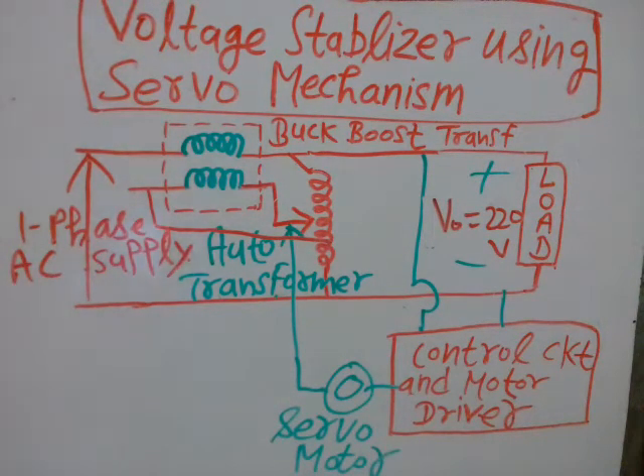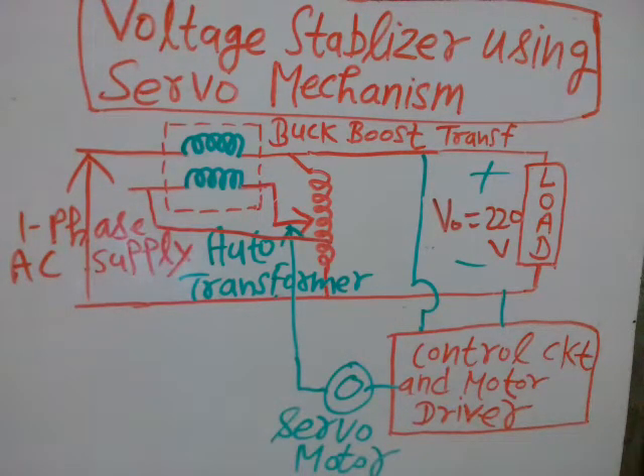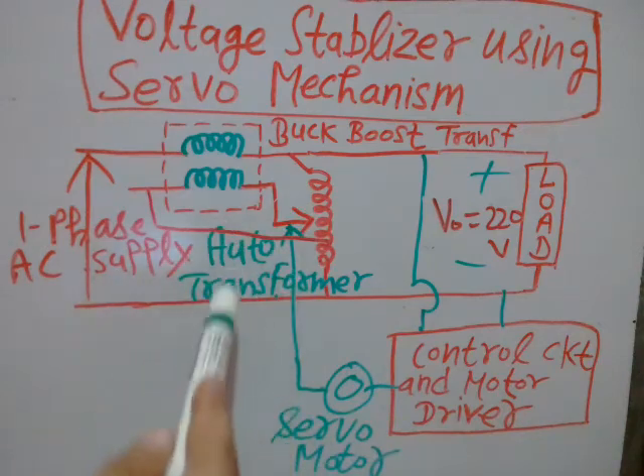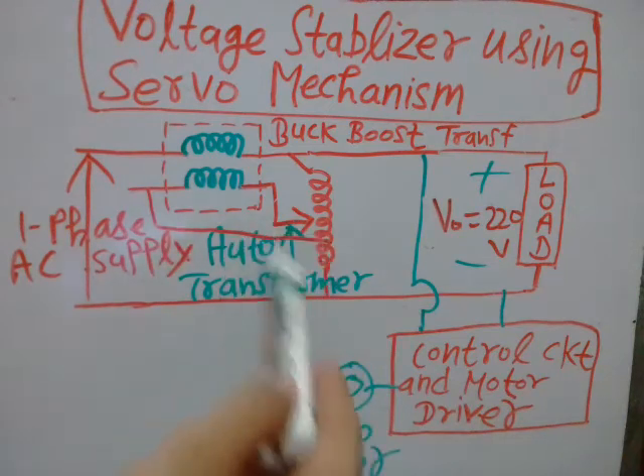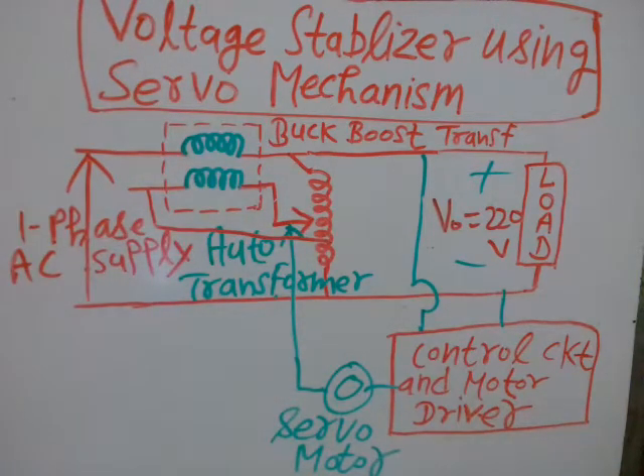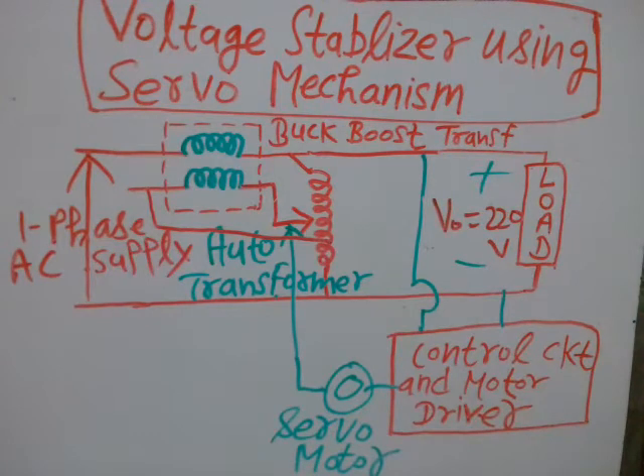The servo motor has two windings — a control winding and a reference winding — with 90-degree phase displacement. This servo motor is connected to a stylus that moves over the toroidal winding of the auto transformer. As the stylus moves, the number of turns changes and hence the voltage changes. The auto transformer is also known as a variable AC voltage source and is used to vary the voltage across the load terminal.